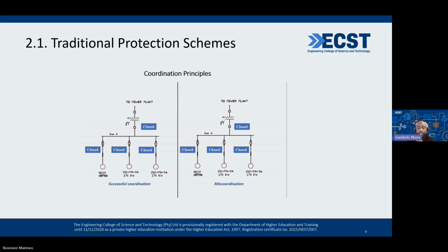But let's say for these three loads, the fault is on the third load. However, it doesn't mean we have to shut the whole thing, because if you look at where the trip is happening, it's at the generator, the main source of power. So we'd be depriving the other two loads of power even though the fault isn't occurring on them.